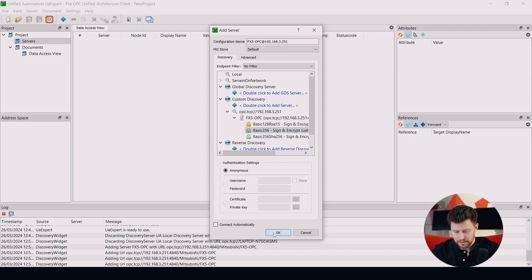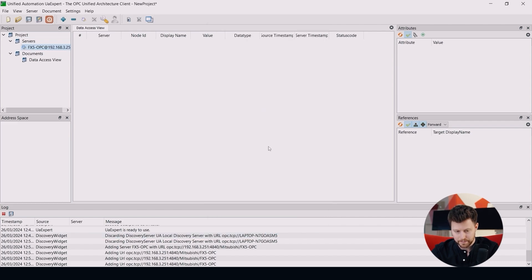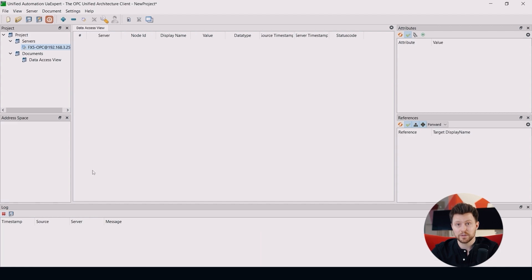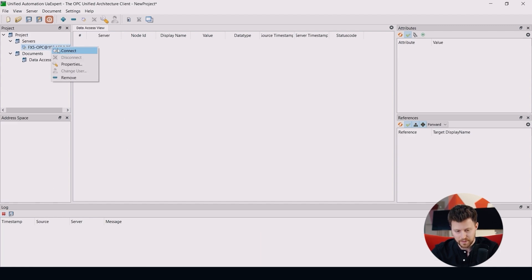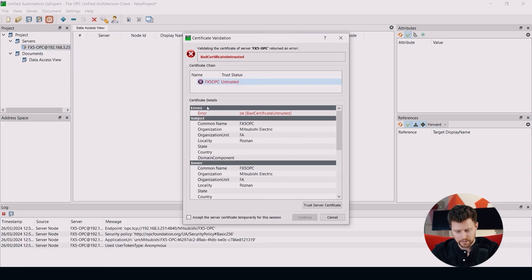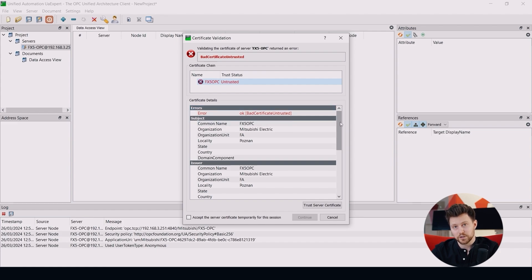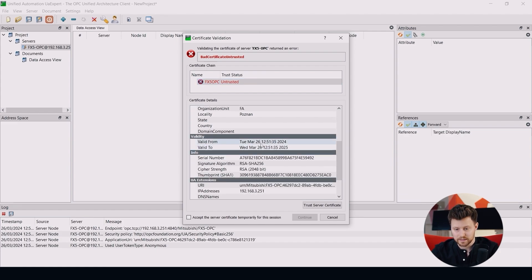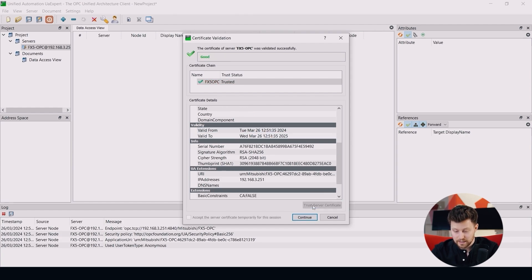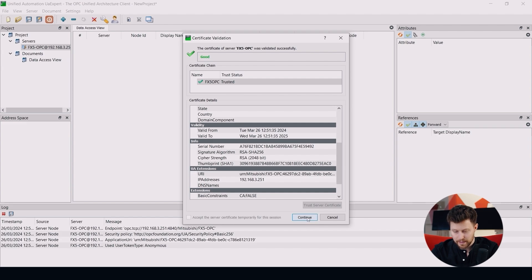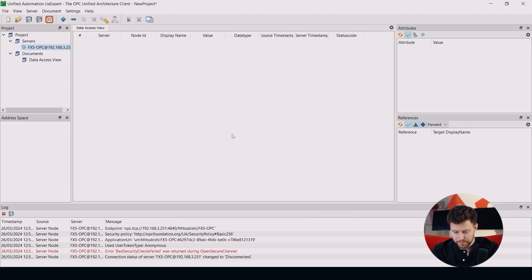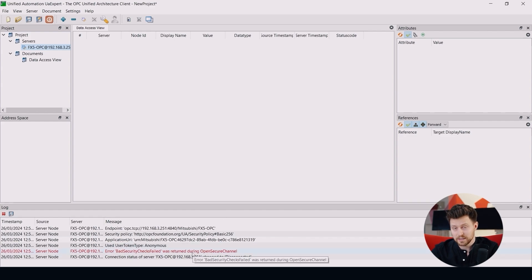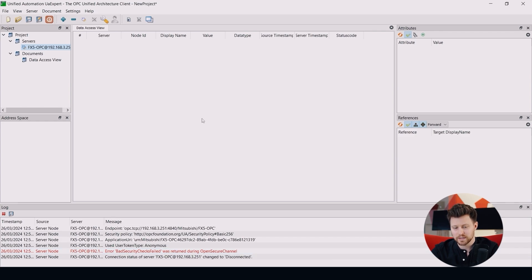So after this, please click OK. And now we can try to connect to our FX5 OPC server. So right click connect. And we can see that the certificate of our server is not trusted by our client. So we can see all the details here. And we can now click trust the server certificates. OK, and now click continue. But we still see that we have some error. This is because we already trusted the server from the client side, but we also have to trust the certificate of our client on our server side.